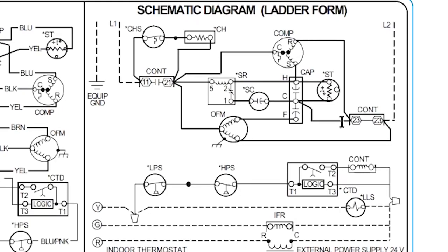The run winding connects directly to L2. Both sides of this contactor are labeled 23 — because it's a solid bar on a single-pole contactor, like a piece of brass or copper. Both top and bottom are the same connection point; we use it as a convenience connection point. So the path is: L1 through common, then run, then L2. On the other side, the start winding is only connected to the circuit through a capacitor, and in this case we have a potential relay type setup.